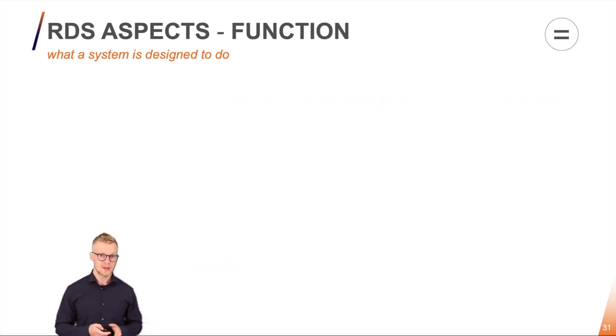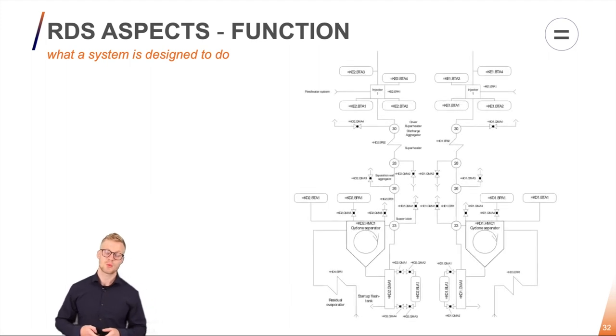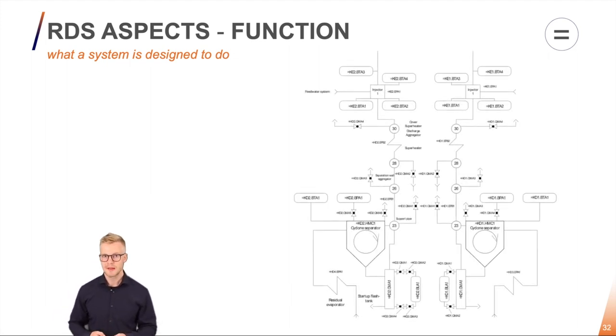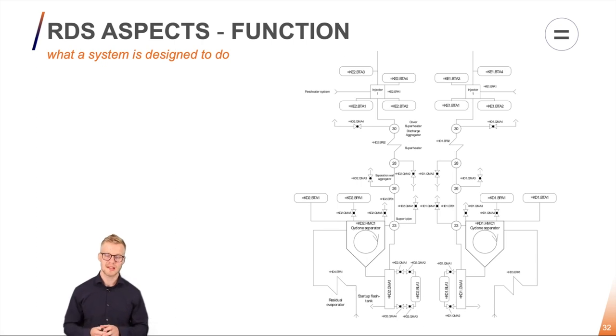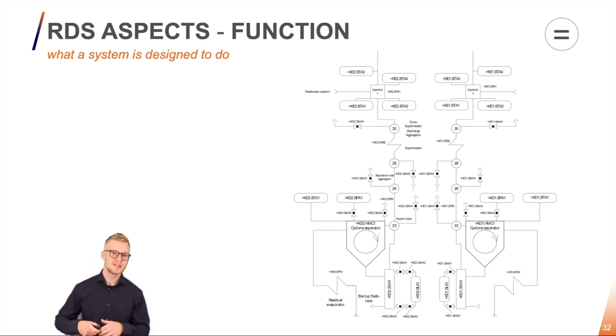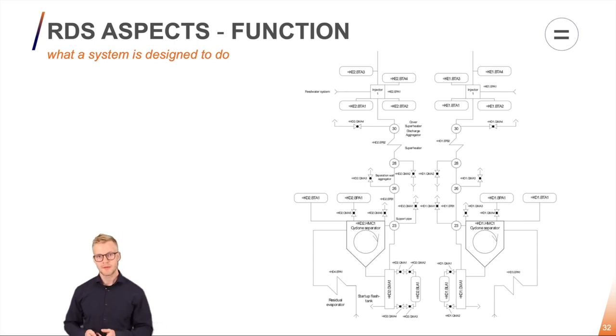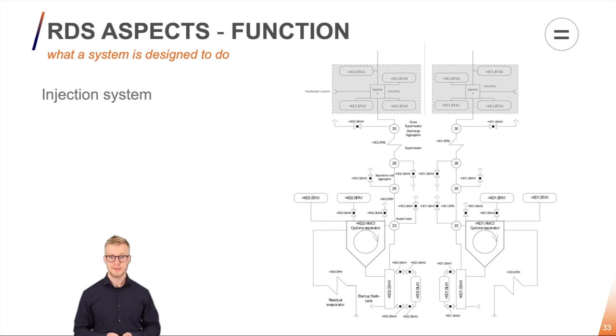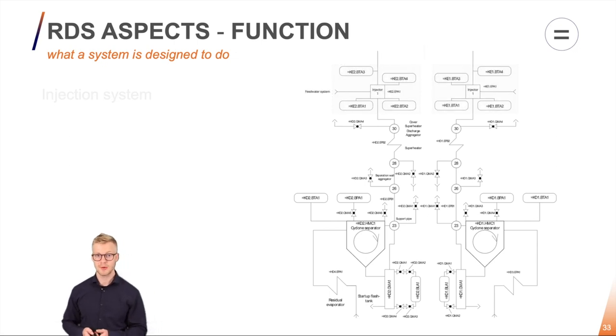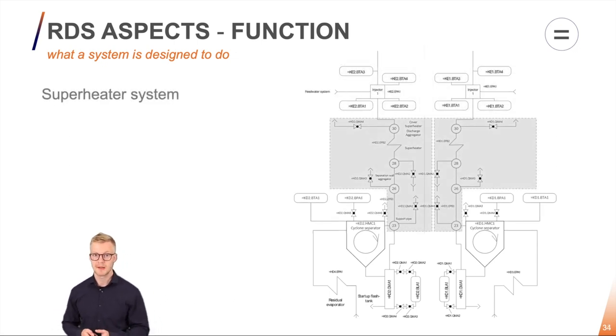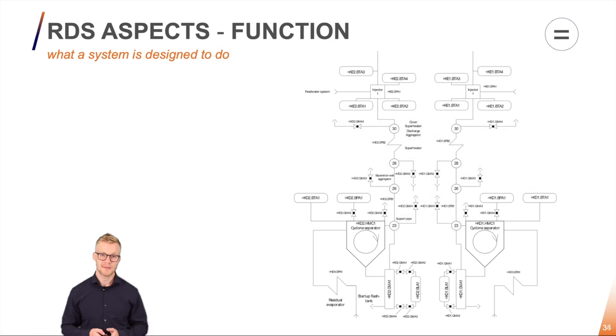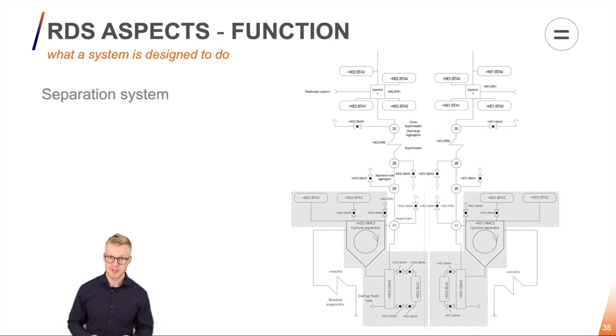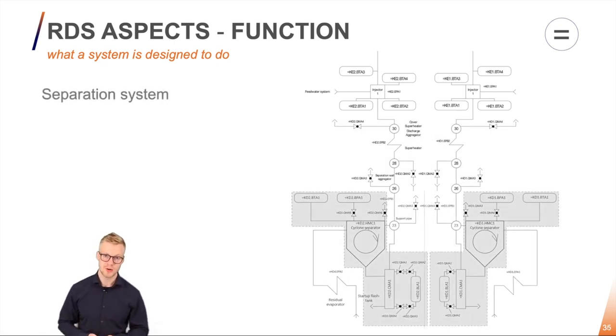In another example here I have a P&I diagram from a power system and here the functional aspect is very good at dividing the P&I diagram into its functionalities so we can see what's actually going on. For example, in the top I have an injection system. In the middle here I have a superheater system and at the bottom here I have a separation system. So suddenly I get a better overview of what's actually going on in my power plant.